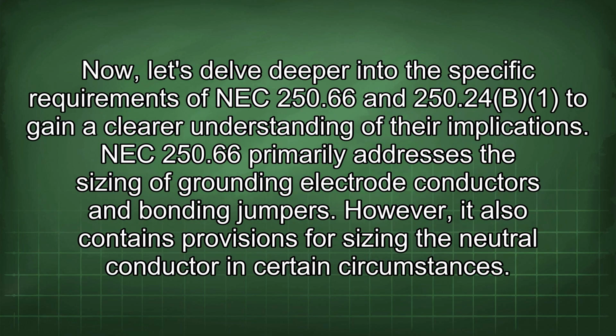Now, let's delve deeper into the specific requirements of NEC 250.66 and 250.24(B)(1) to gain a clear understanding of their implications. NEC 250.66 primarily addresses the sizing of grounding electrode conductors and bonding jumpers. However, it also contains provisions for sizing the neutral conductor in certain circumstances.